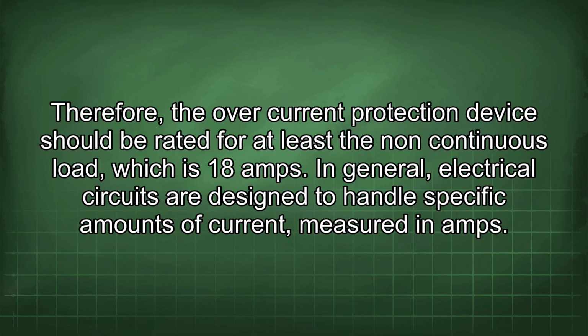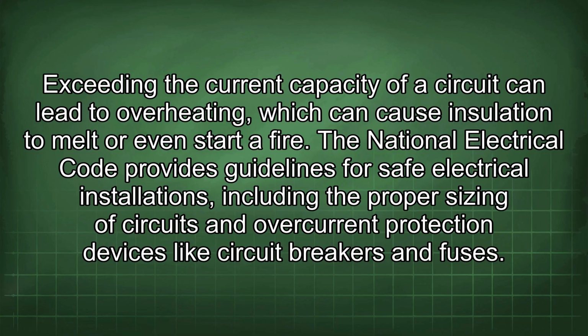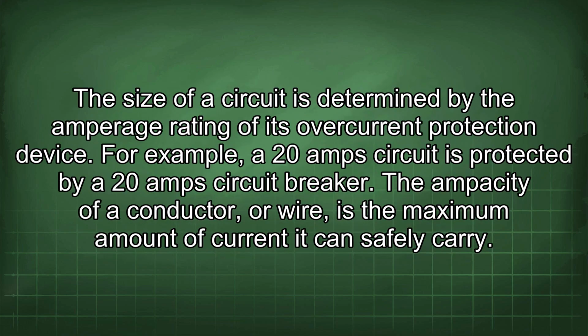In general, electrical circuits are designed to handle specific amounts of current measured in amps. Exceeding the current capacity of a circuit can lead to overheating, which can cause insulation to melt or even start a fire. The National Electrical Code provides guidelines for safe electrical installations, including the proper sizing of circuits and overcurrent protection devices like circuit breakers and fuses. The size of a circuit is determined by the amperage rating of its overcurrent protection device. For example, a 20 amp circuit is protected by a 20 amp circuit breaker.